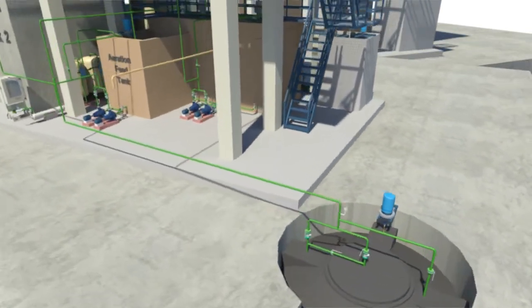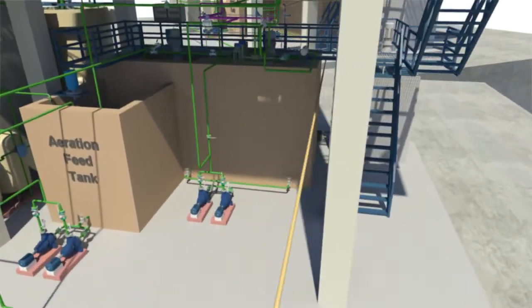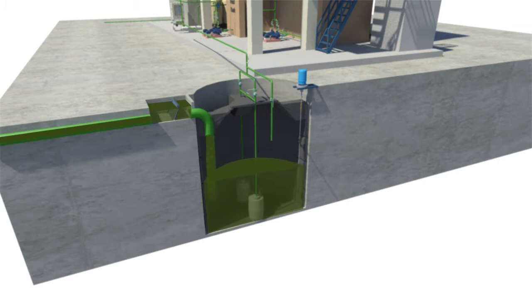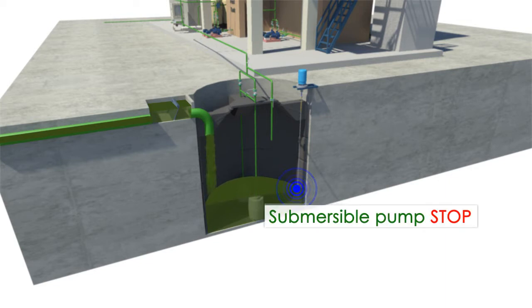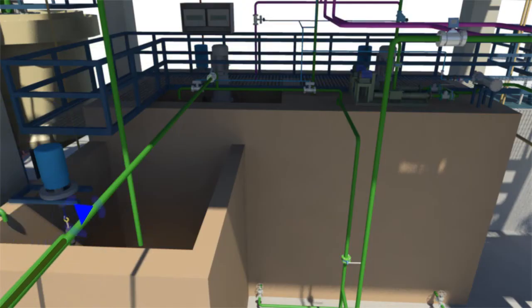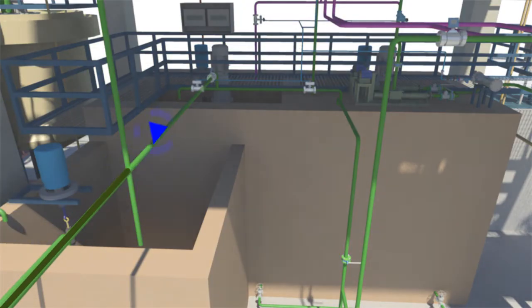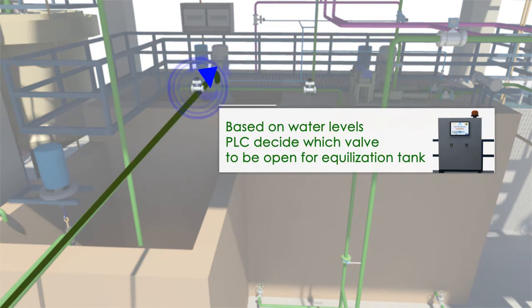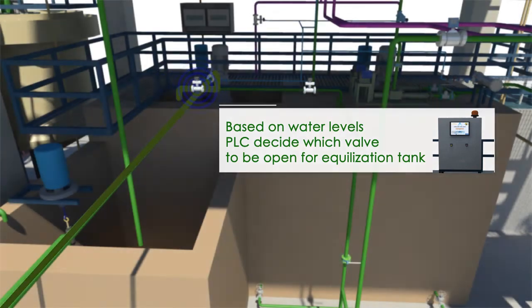On detection of an adequate quantity of wastewater, the level sensor activates the controller, which automatically starts the submersible pump. Based on input from the level sensor of the equalization tank, the PLC decides which valve is to be opened and discharges effluent into it.